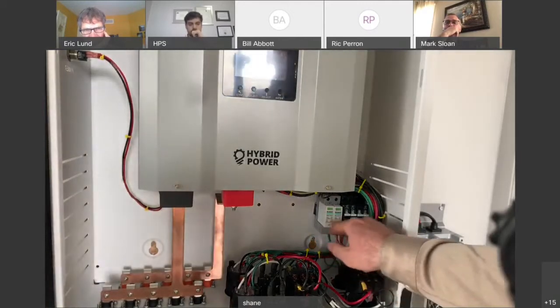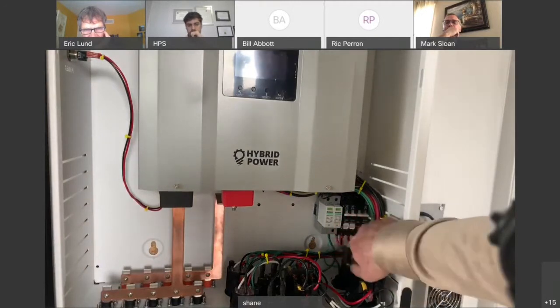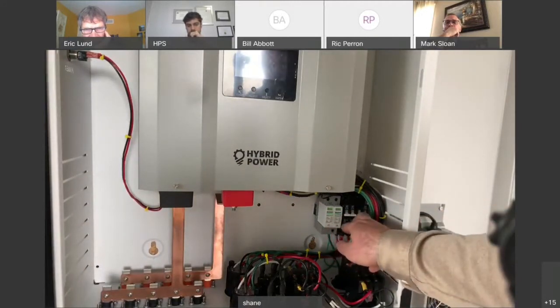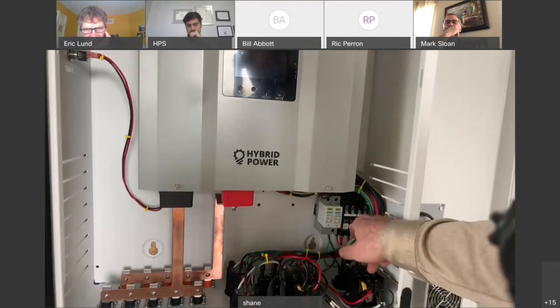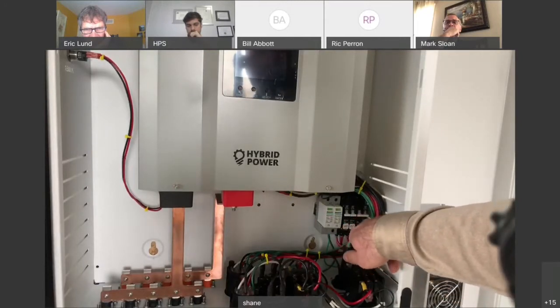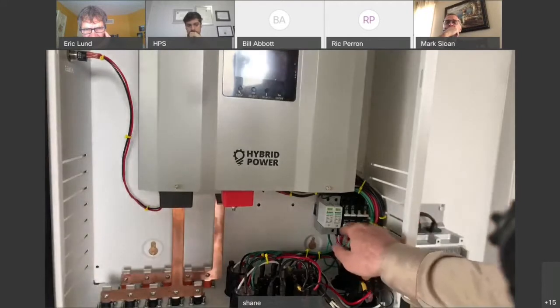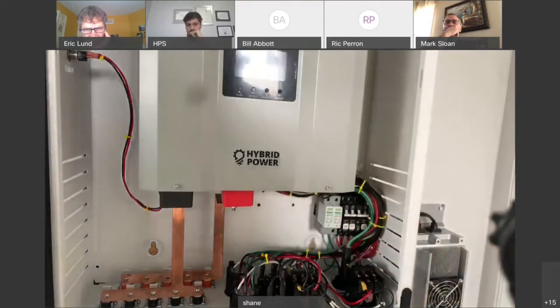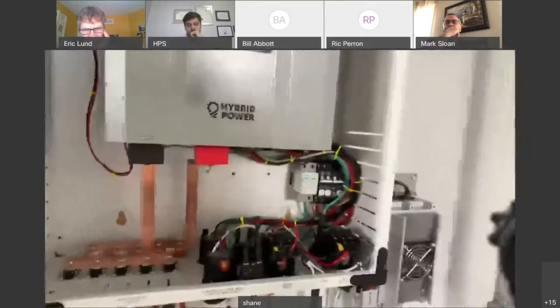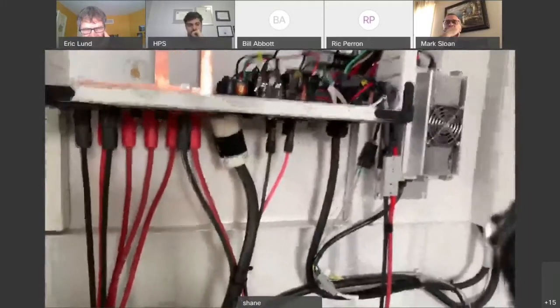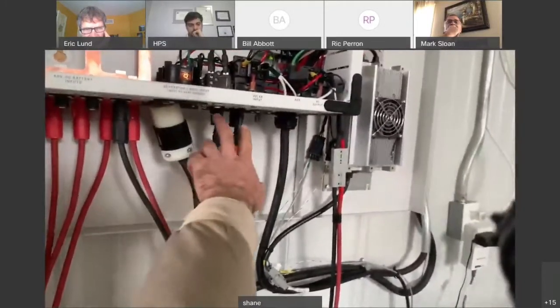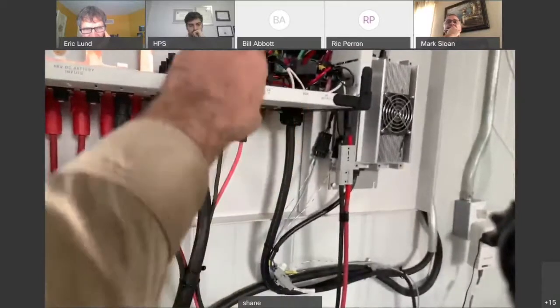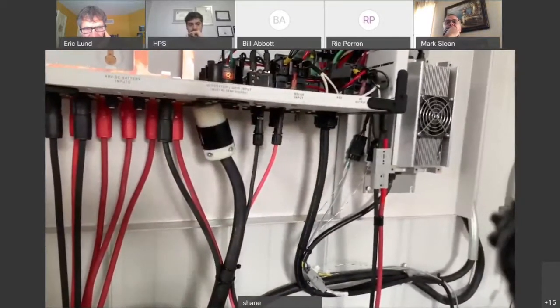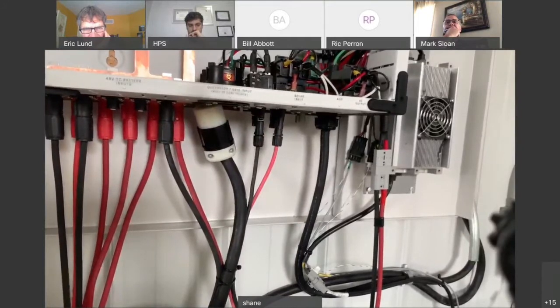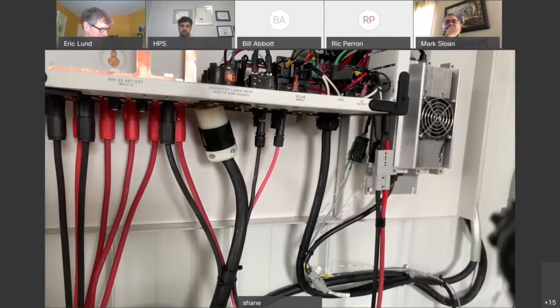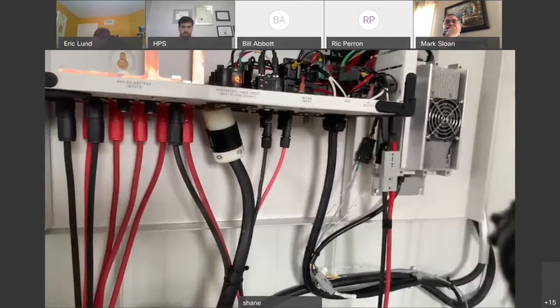Here we have surge arresters for our PV side, and then we have our 4 breakers. We have 2 30 amp inputs, a 63 amp master output, and then a 0.5 ground fault detection. So the 2 30 amp inputs are fed from MC4 connectors, which are underneath. You can see here there's 2 sets. There's a front set and a back set. Both go individually to a breaker. Now I'm just going to do a quick overview, and then we'll go through the optimal installation and how I like to size my systems for quick installations. So while we're under here, we can take a look at other things.